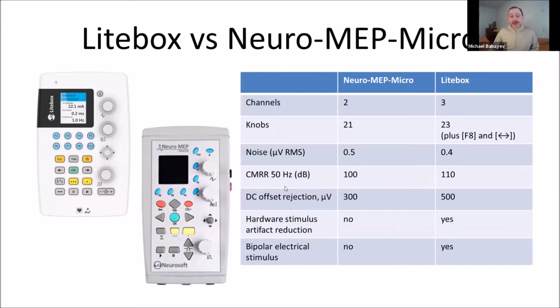Another very important parameter for the device is CMRR, or common mode rejection ratio. It is about how the device can reduce interference noise, so noise from the power supply, 50 Hz or 60 Hz. And in Neuro-MEP-Micro, it is 100 decibel, and in Litebox, it is 110. In Litebox, it's 10 decibel bigger, but 10 decibel means 3 times better. So the interference from the mains supply in Litebox will be 3 times lower than in the Neuro-MEP-Micro.